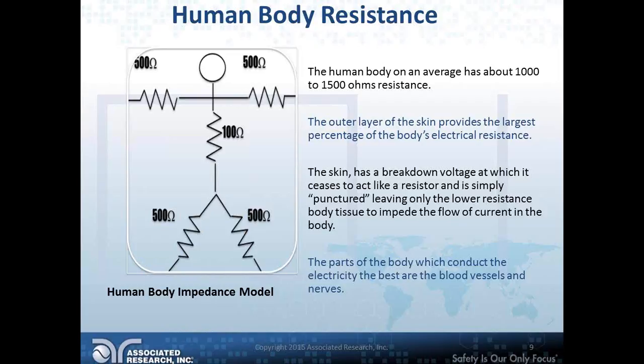Keep this human body impedance model in mind as you set up your workstation, train your operators, and go through this presentation with them. This model assumes a pretty large contact area when saying 1,000 to 1,500 ohms - the equivalent of grabbing conductors with both hands, each about the size of a Coke can. So that range assumes whole hand contact on something fully conductive and energized.